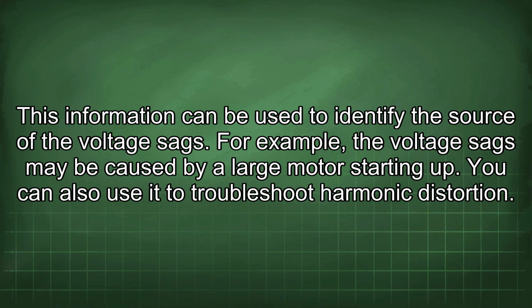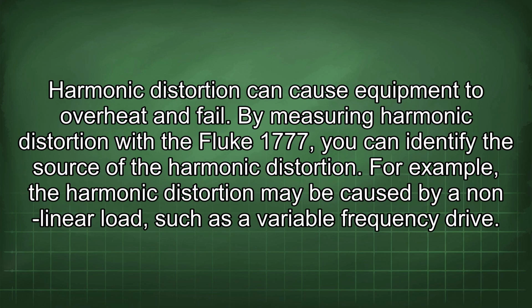You can also use it to troubleshoot harmonic distortion. Harmonic distortion can cause equipment to overheat and fail. By measuring harmonic distortion with the Fluke 1777, you can identify the source of the harmonic distortion. For example, the harmonic distortion may be caused by a nonlinear load, such as a variable frequency drive.